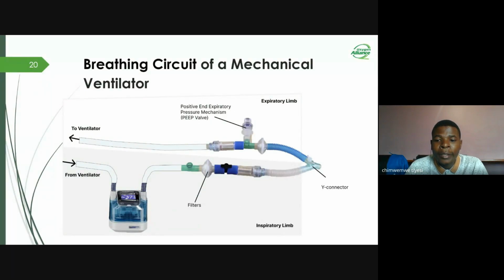To enhance patient comfort, the mechanical ventilator also has a heat and moisture exchanger, which some just call a humidifier. It is often placed within the inspiratory limb. This heat and moisture exchanger warms and humidifies the incoming gas, mimicking the natural condition that occurs in the upper airways of the respiratory system. This helps to prevent the respiratory passages from drying out and also ensures a more comfortable ventilation experience.